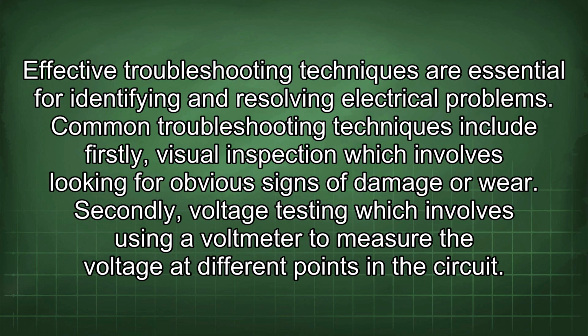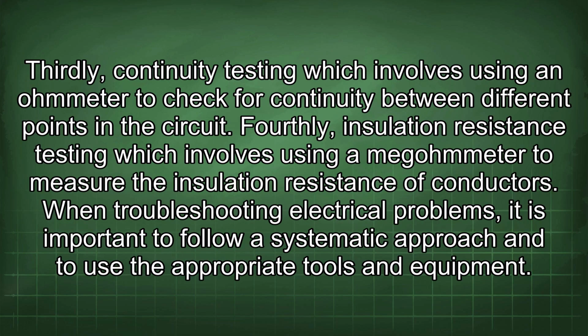Effective troubleshooting techniques are essential for identifying and resolving electrical problems. Common troubleshooting techniques include, firstly, visual inspection, which involves looking for obvious signs of damage or wear. Secondly, voltage testing, which involves using a voltmeter to measure the voltage at different points in the circuit. Thirdly, continuity testing, which involves using an ohmmeter to check for continuity between different points in the circuit. Fourthly, insulation resistance testing, which involves using a megohmmeter to measure the insulation resistance of conductors. When troubleshooting electrical problems, it is important to follow a systematic approach and to use the appropriate tools and equipment.